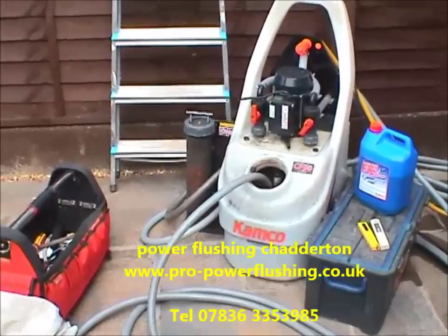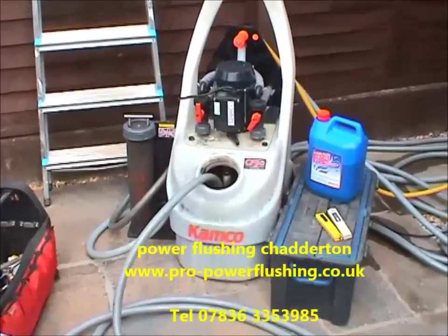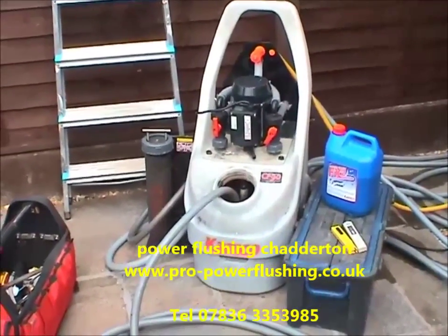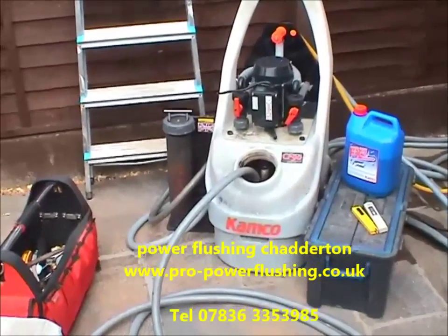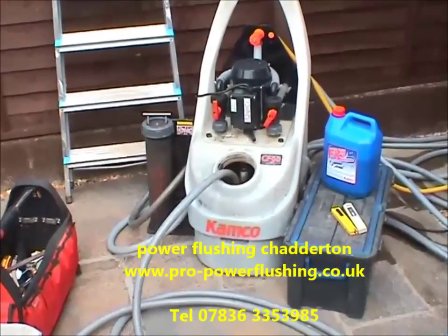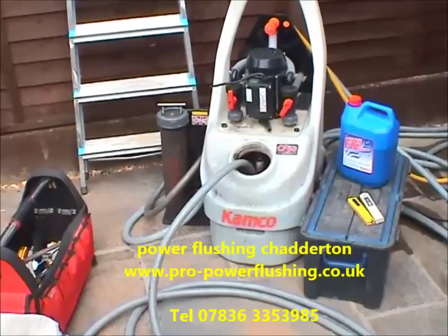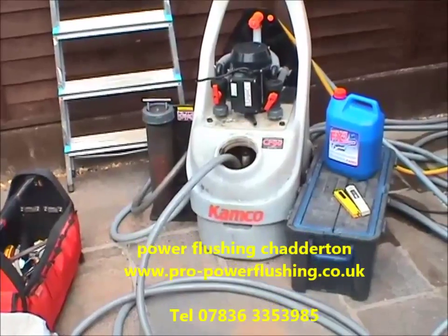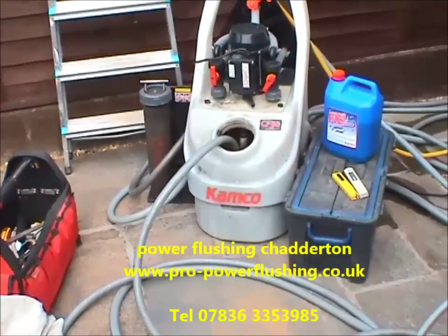The system's a combination boiler. We're actually in the summertime now, so it's quite a good idea to get the system power flushed before people start getting cold in the winter and start rushing around trying to get the system power flushed. The customer had a new boiler fitted recently. The engineer didn't power flush the system. The water is absolutely filthy and the customer's complaining of some cold radiators.